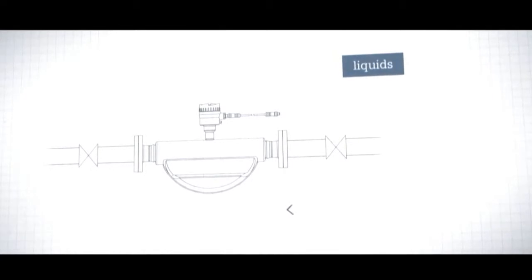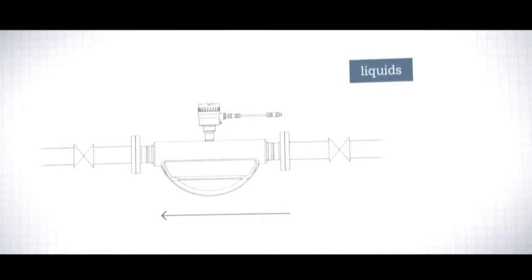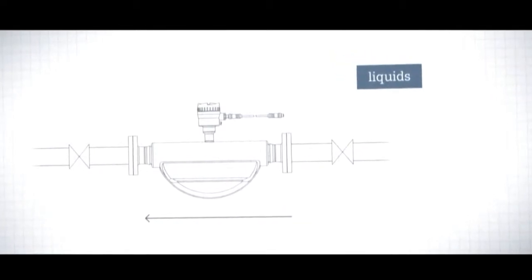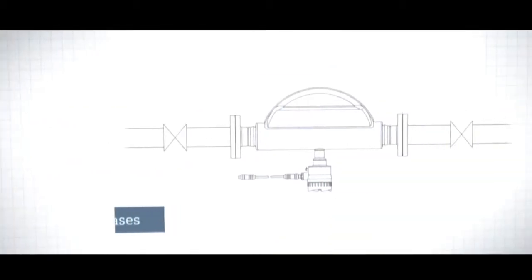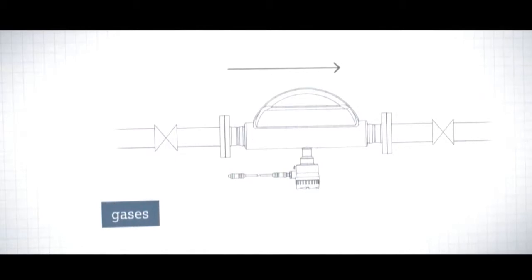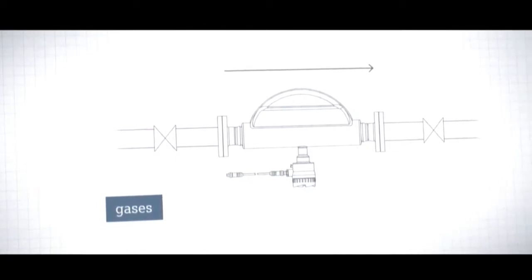For liquid applications we recommend a horizontal mounting position with the inner pipes of the sensor facing downwards. For applications involving gases, we recommend a horizontal mounting position with the pipes facing upwards.